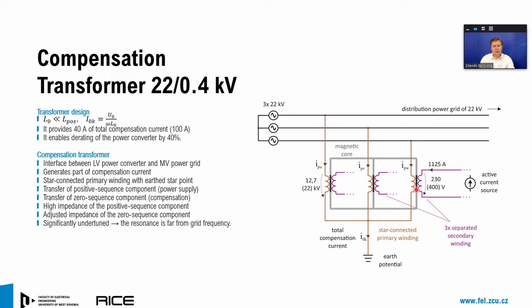A very important feature of the configuration is also that we operate the system significantly undertuned. It means that the resonance frequency given by the zero sequence impedance of the transformer acting with the grid capacitance is significantly below the operating frequency of the grid, which has positive impacts in reduced asymmetry of the grid and a reduced zero sequence component of the voltage.